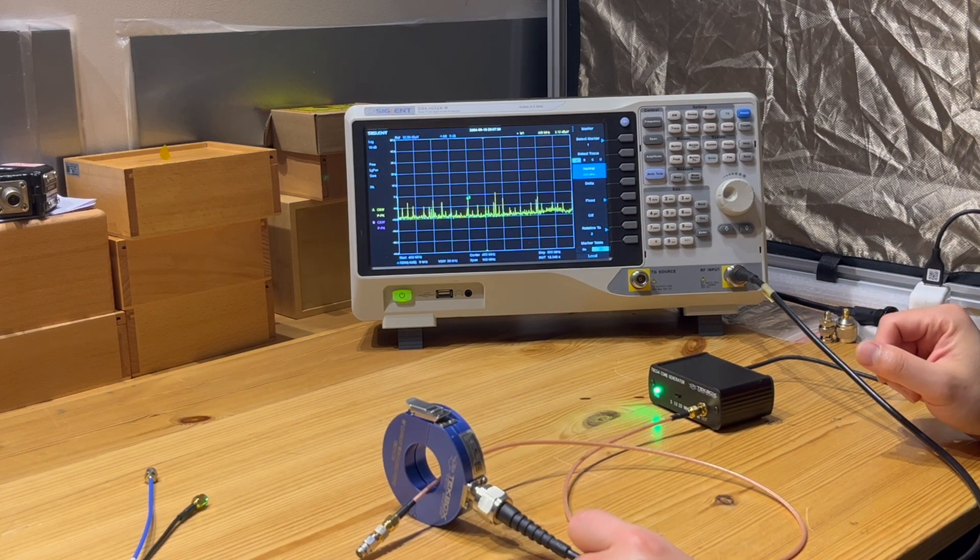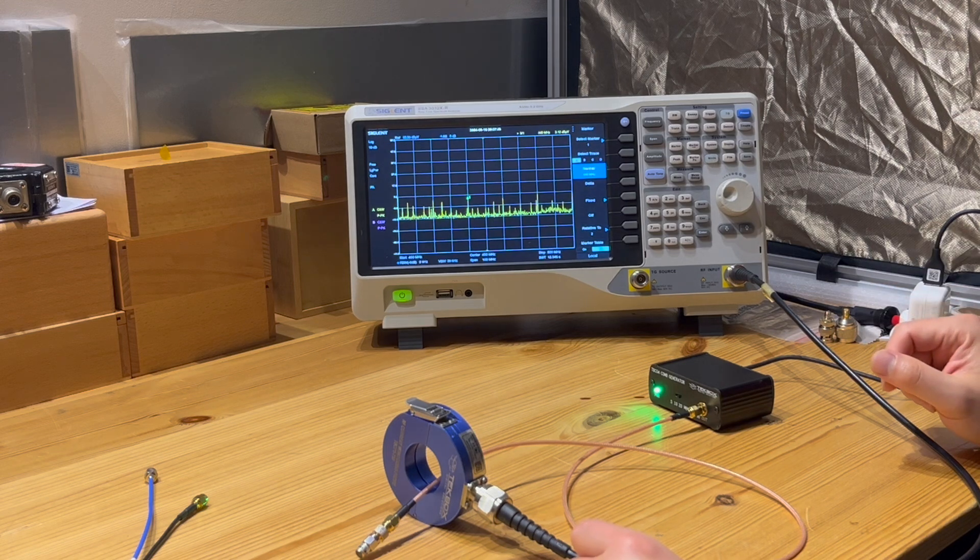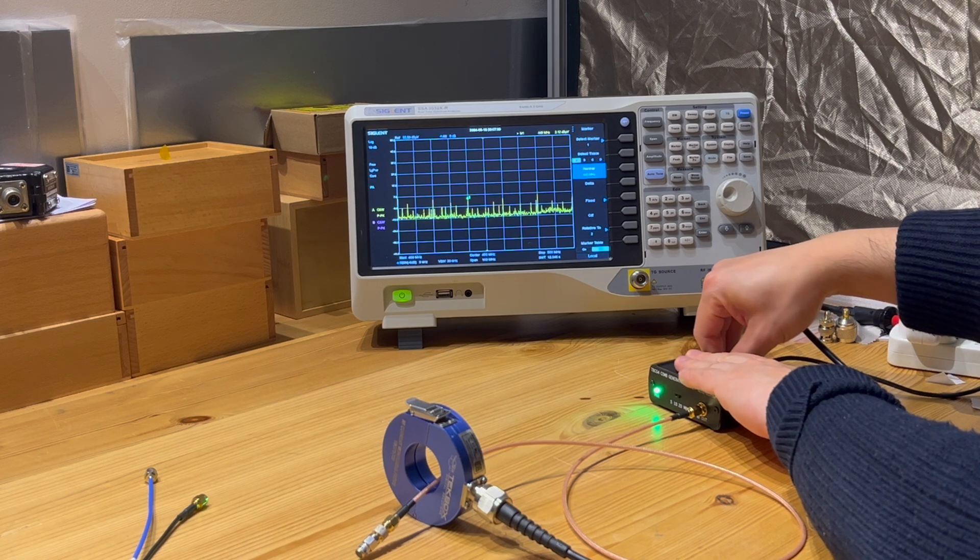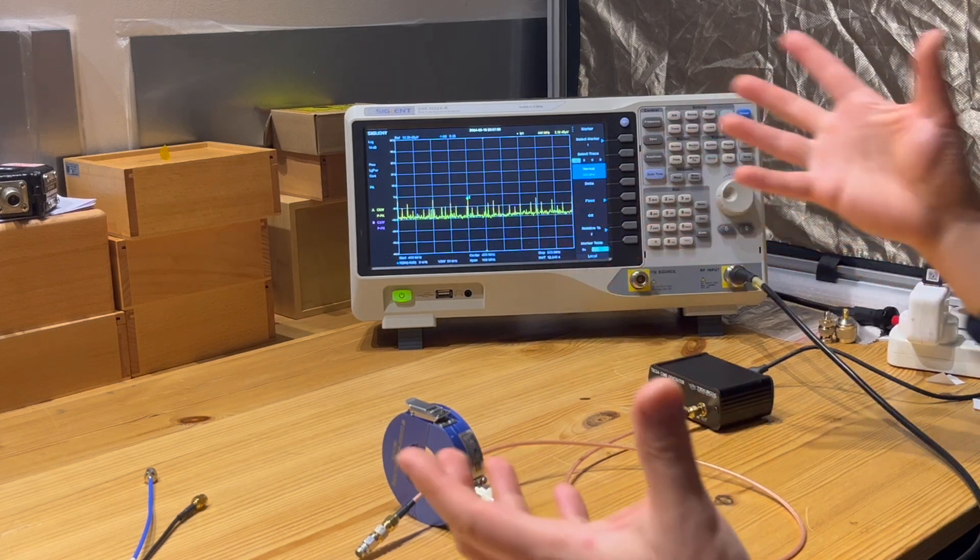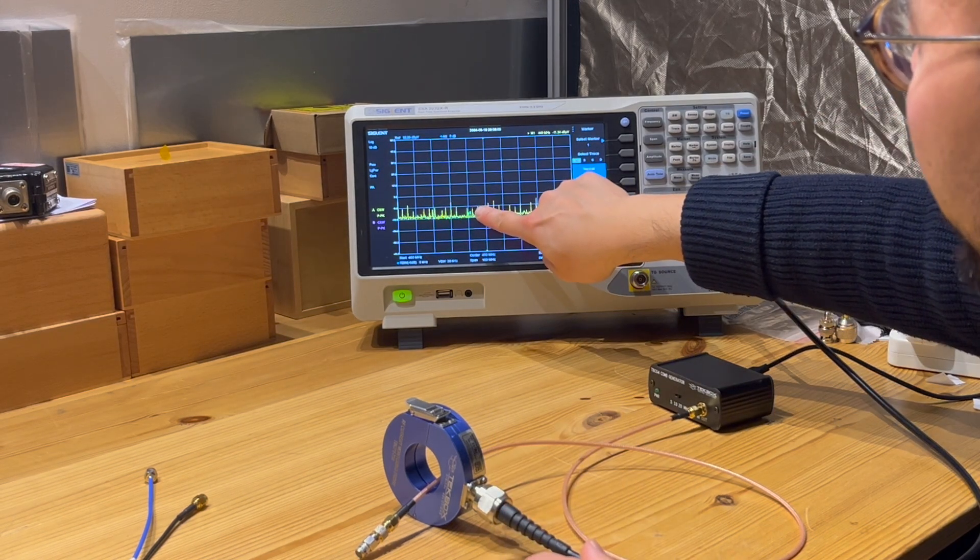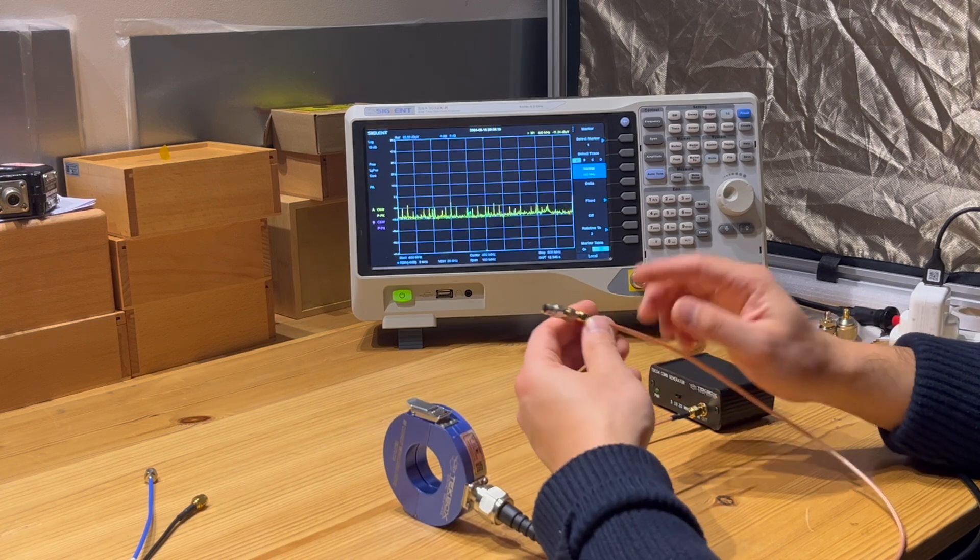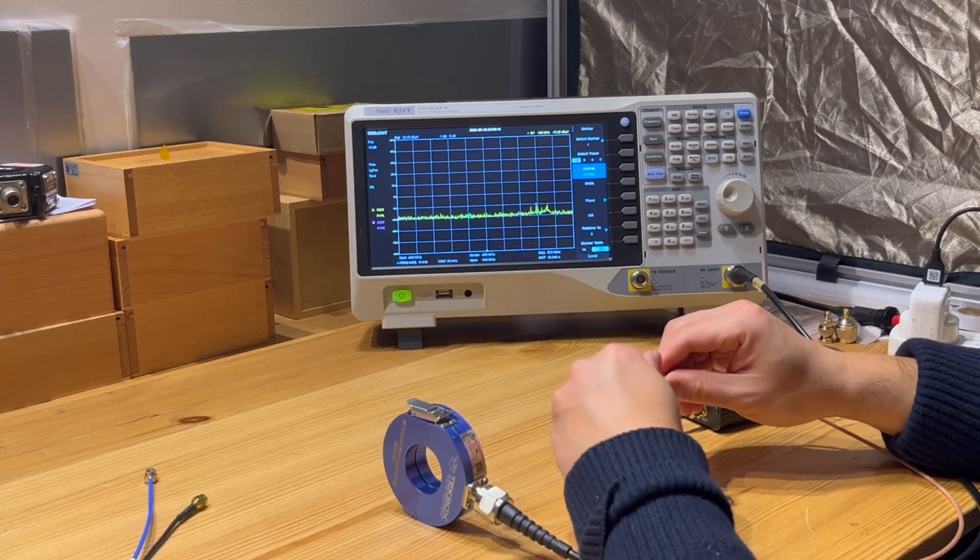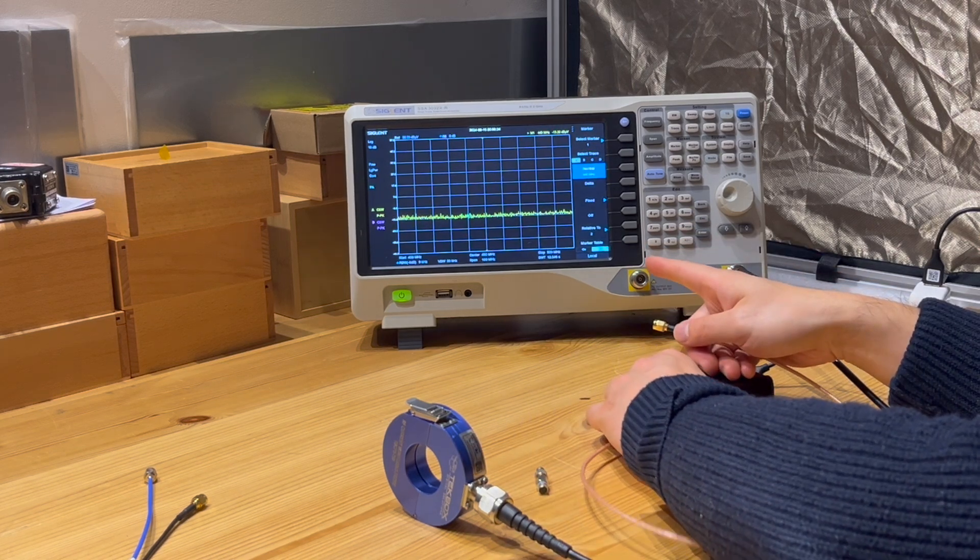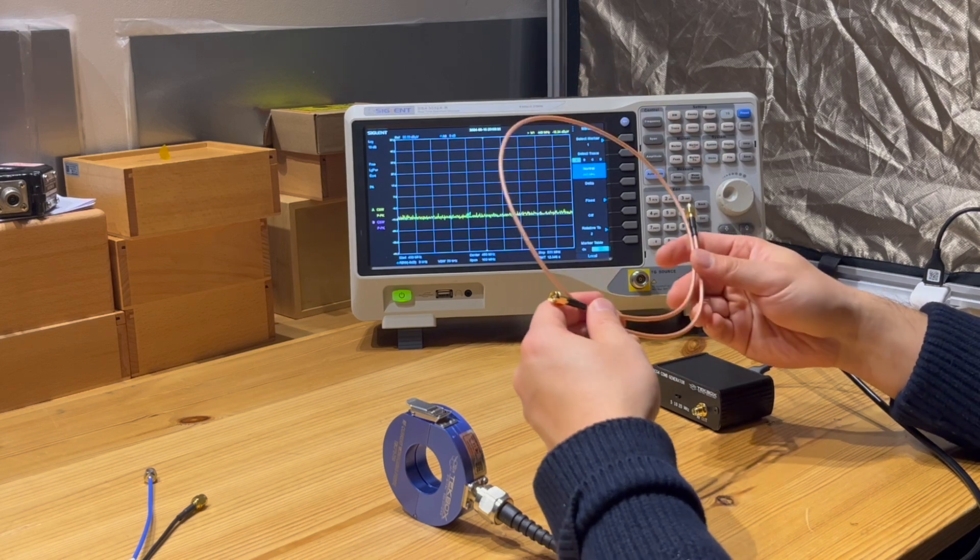And this noise level is about, if I put the marker here for example, that is 440 megahertz and I picked up about 2 dB microvolts. So that must be the noise leaking out of this coaxial cable. In order to prove that let me disconnect the power of the comb generator and see if you see that disappear. That is disappearing, this disappeared again. So the other noise is just ambient noise. What we focus on is 420, 440 - you can see 440 actually disappeared. So we did measure some noise on the outside of this shielded cable. This indicates the performance of this shielded cable - as we measure it is about two to three dB microvolts picked up.